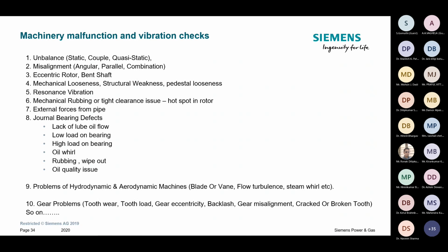Then mechanical looseness, weakness or pedestal looseness is also very common. You can see it in normal life too, where a motor or pump's feet are not properly tightened, or the bolts are loose, or the foundation is weak. Over a period of time, the foundations settle down because they are supported on concrete pillars, and these are big pillars, but after 20 years they sag and go down, by only 0.1, 0.2 mm. So the relative height between pillars is different, and because of that you will have eccentricity or excitation in the system. So that is one reason.